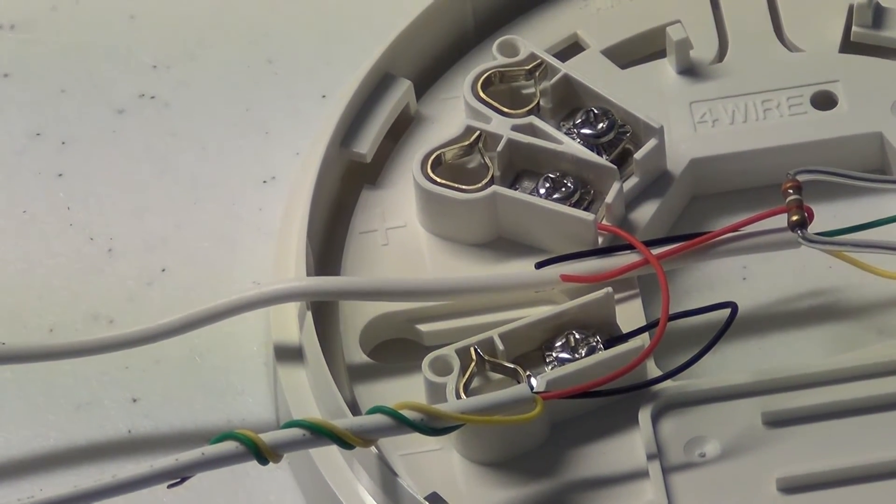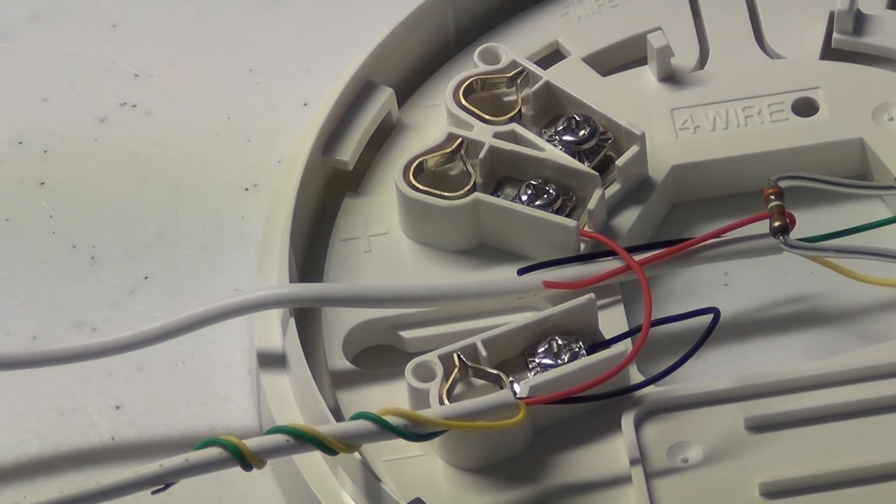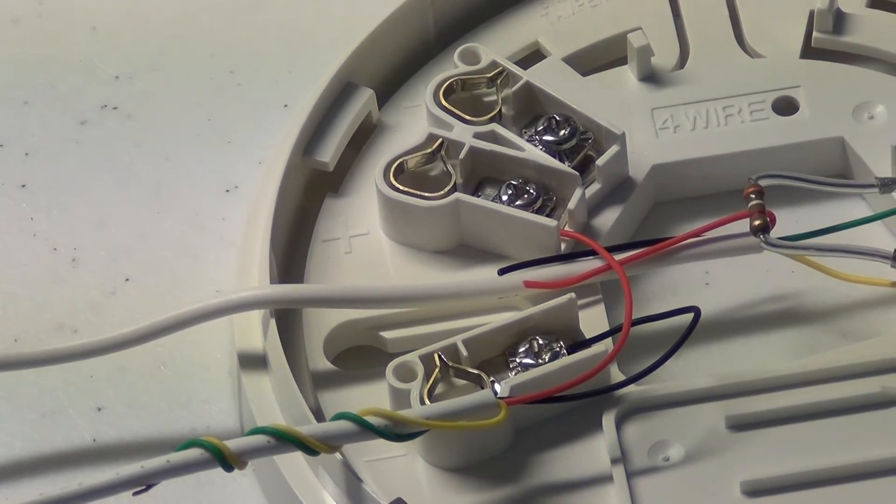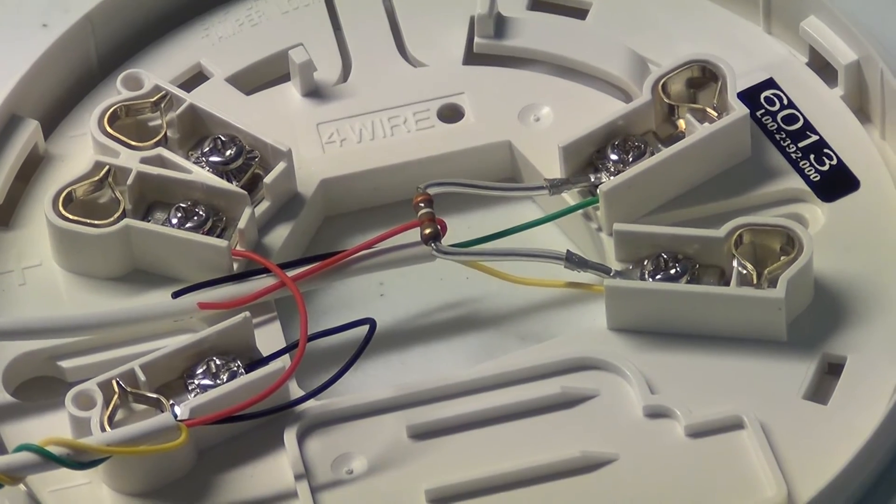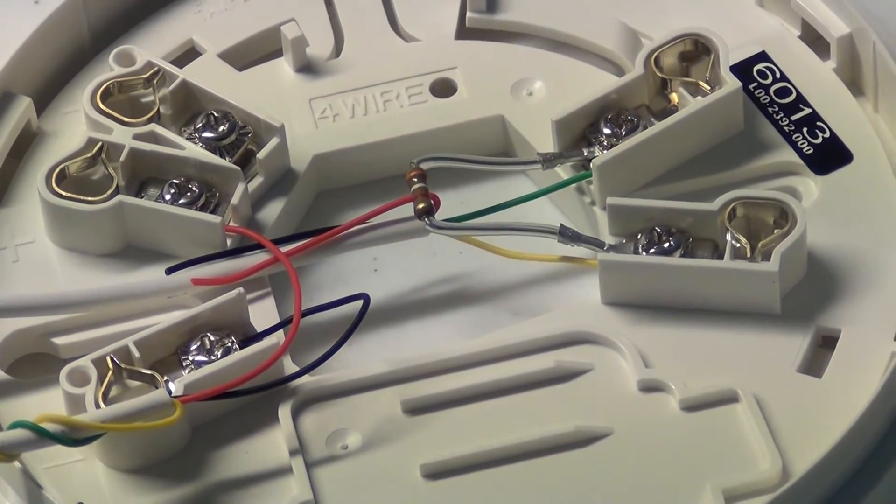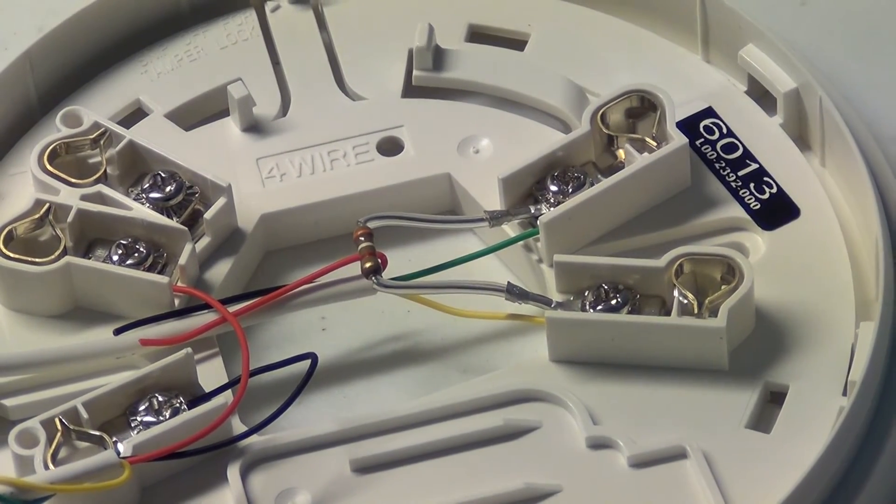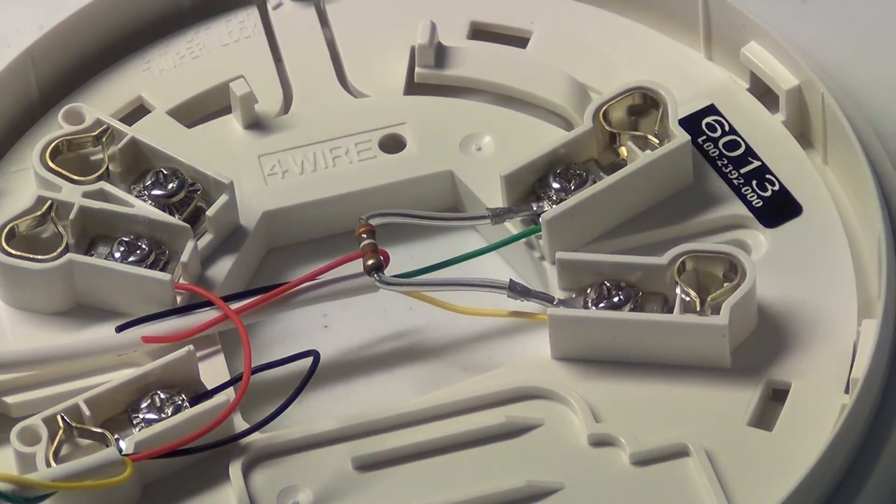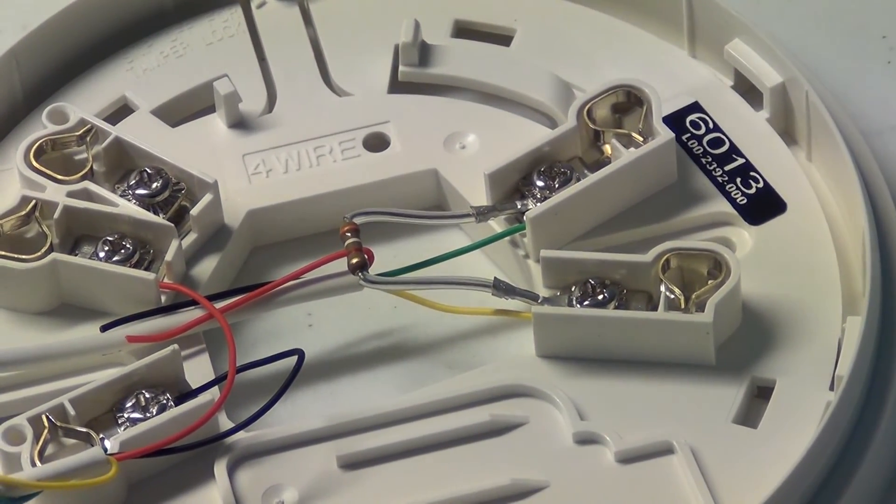So your second positive post on your first smoke CO to your first positive post on your second CO smoke combo and so on and so forth. And then System Sensor has told me that if you're doing more than one smoke CO combo you will just basically run your wires straight to the other terminals on your next smoke CO combo unit.